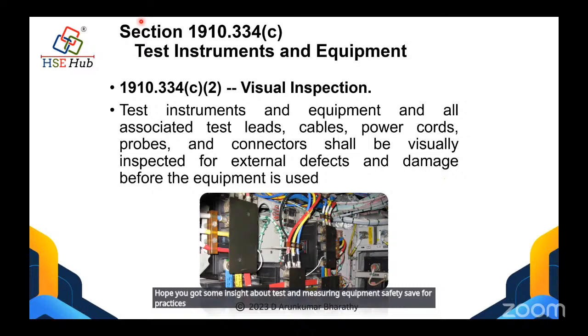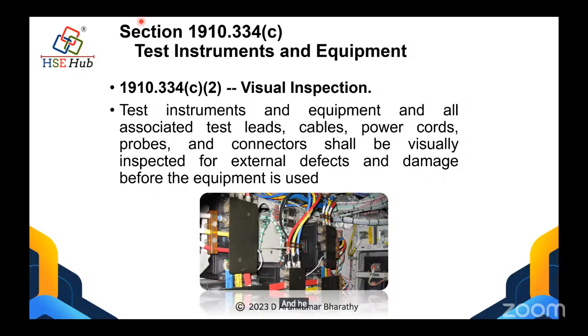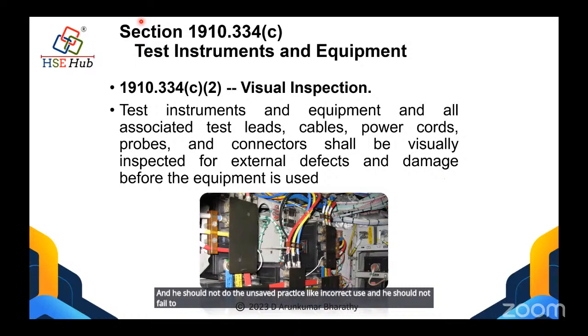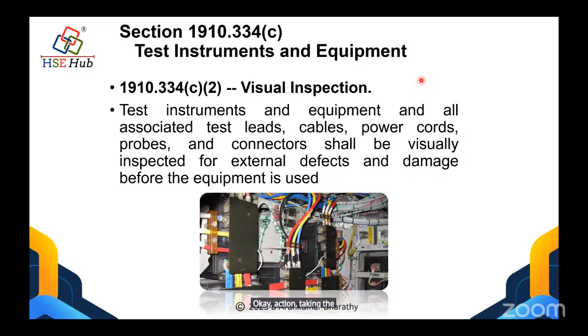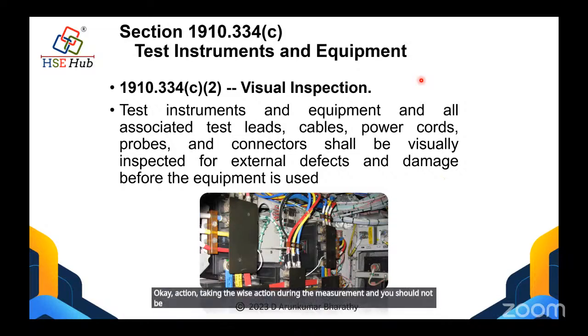Okay, to sum it up again: first, the person must be qualified in understanding the proper selection, rating, and category of the instrument. He should not do unsafe practices like incorrect use, and should not fail to inspect. He should know how to use it in different environments like a confined space, a flammable area, or an explosive area. He should also demonstrate safe practice by keeping the instrument away from his body and taking wise action during the measurement. He should not be in a hurry, and he should follow the arc flash boundaries whenever we open the panel and measure, right?